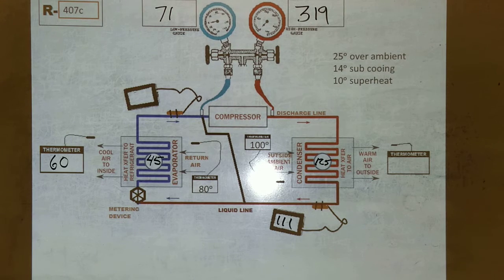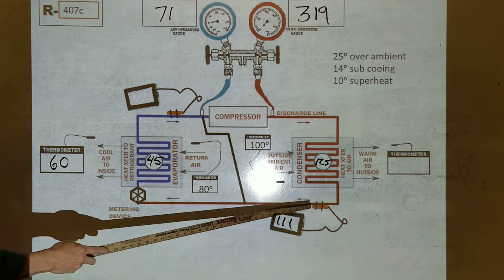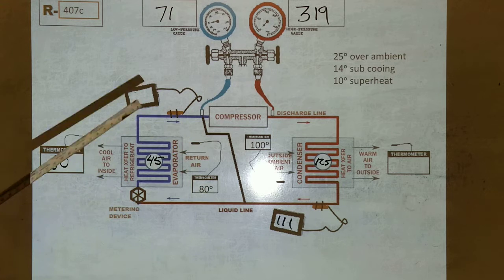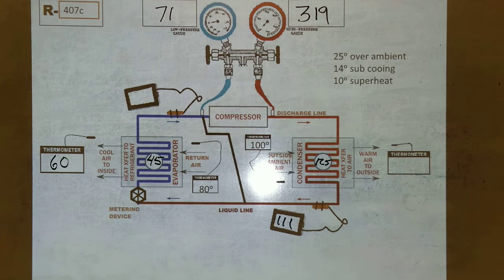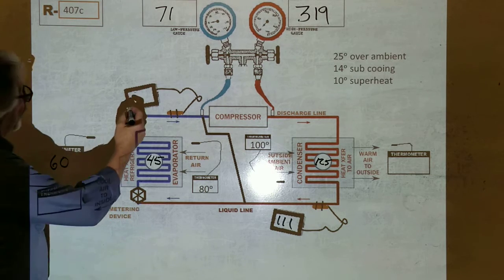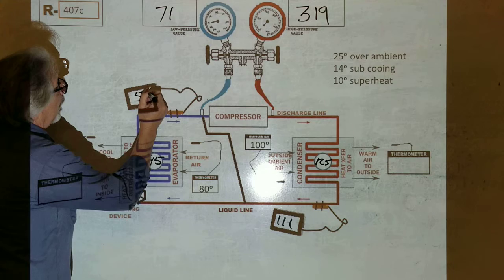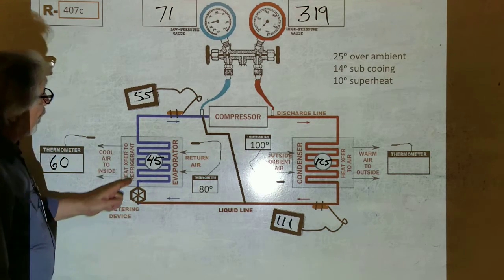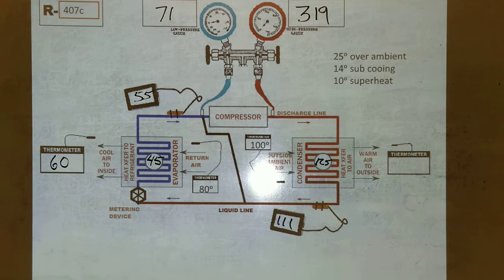So we should be seeing 111 degrees on our liquid line. What about our suction line now? 55? We have 10 degrees superheat. Yeah, 55. 45 plus 10 equals 55, right? Got that? Yes.